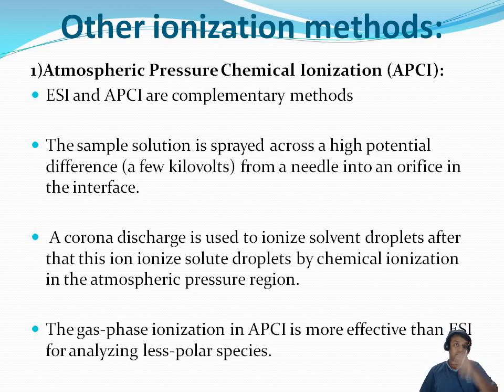This is the basic figure of APCI. The liquid is passed along with a nebulizing gas, which is released at high pressure. When the gas comes in contact with the liquid, it reaches the heater, and at the heating stage the corona discharge needle releases electrons. When these electrons come in contact with your sample solution, in the presence of the vapor and gases at atmospheric pressure, the solvent ions are converted into solute ions. The electrons bombard the solute, and finally it is converted into cations.